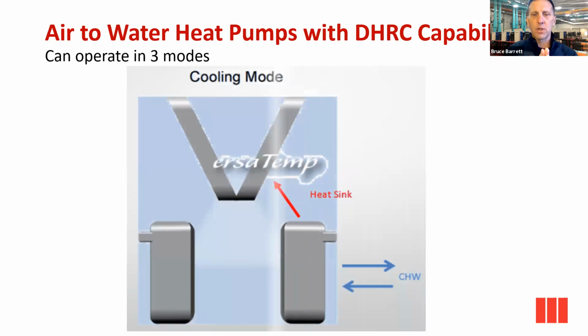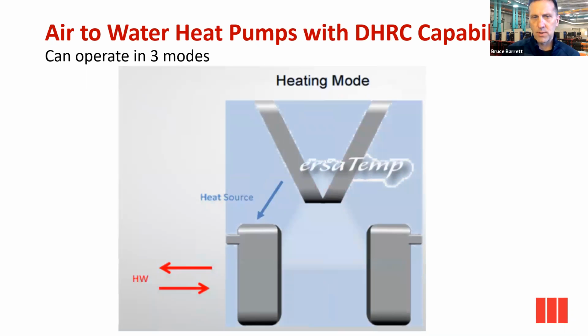All right, let's look at the 3 modes. Important to understand these. So we've got 3 different modes. Cooling mode, it's operating identically to an air-cooled chiller. We're extracting heat from our evaporator side. We're discharging that heat to the coil. Simple. The second mode, heating mode, it's an air source heat pump. We're extracting heat from the air, again, down to about 40-degree ambient, and we're adding the heat of compression to make hot water out of our condenser braze plate heat exchanger. The air is our heat source, and we're adding heat of compression.